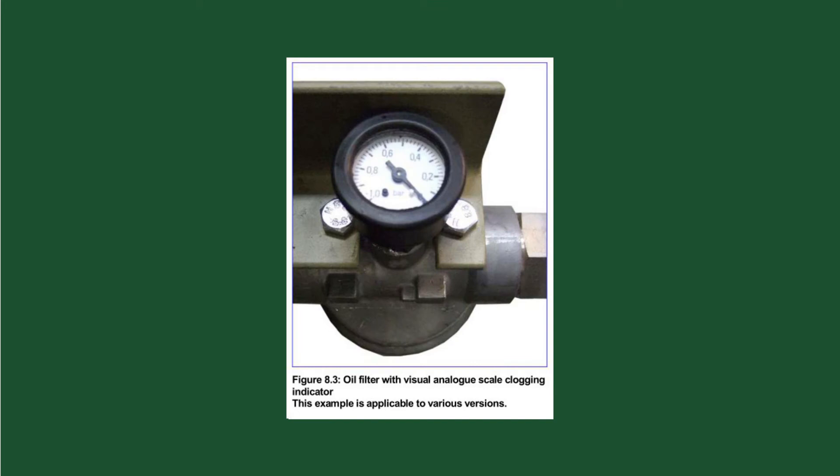The M6 suction filter is equipped with a visual analog scale clogging indicator. During stoppage of the oil pump, the pressure shall indicate 0 bar. Under normal operating conditions, between 0 and negative 0.7 bar, while negative 0.7 to negative 1 bar means clogging, the filter element should be replaced.